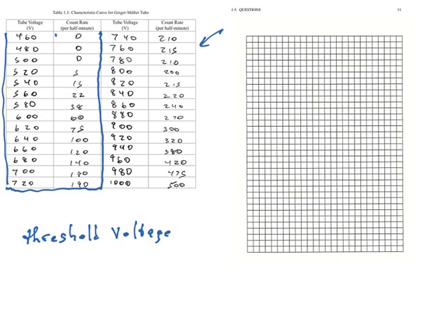And if you notice, in general, as I increase the voltage, the number of counts I get increases as well. Again, it makes sense. Increasing the voltage makes it more sensitive. If it's more sensitive, it can detect more. But notice something. Let's start looking at 740.